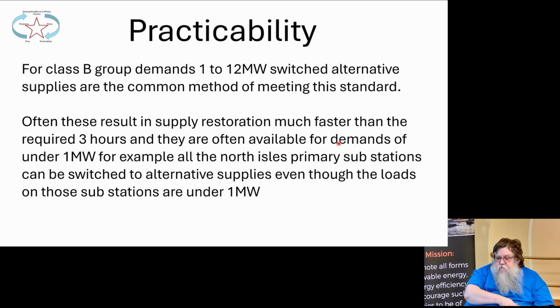Class B, group demands of 1 to 12 megawatts. Switched alternative supplies are the common method of meeting this standard. Often you meet the standard in less than 3 hours, and they're often available for demands of under 1 megawatt just because of how easy it is to build the system. All the North Isles primary substations can be switched to alternative supplies, even though the loads on these substations are under 1 megawatt. So if you lose a supply to a substation, you can switch it round to another one, and you're better than the standard basically.